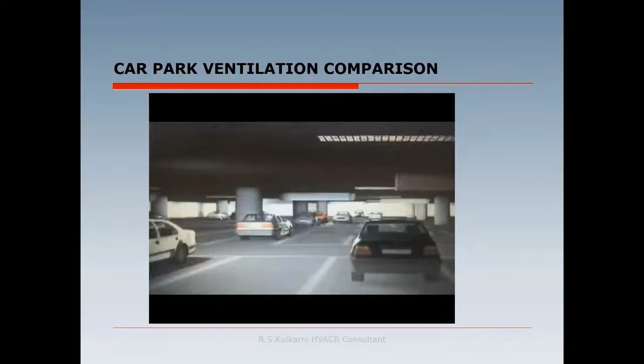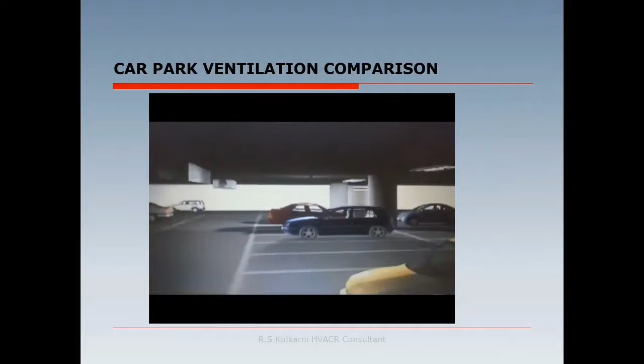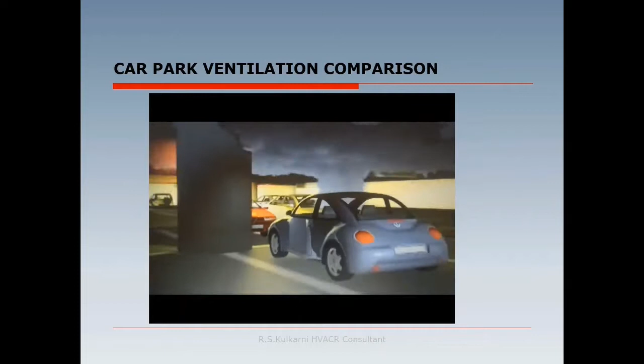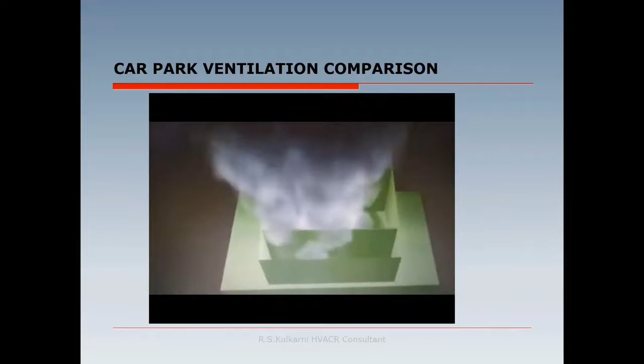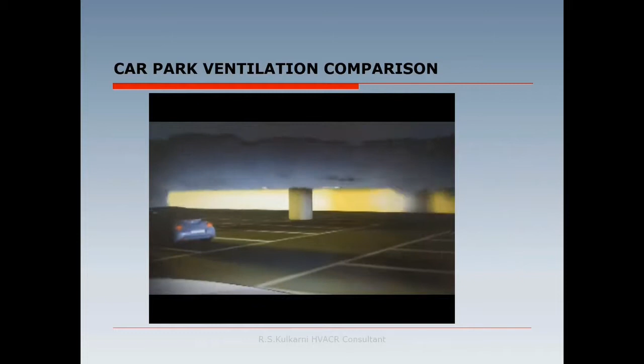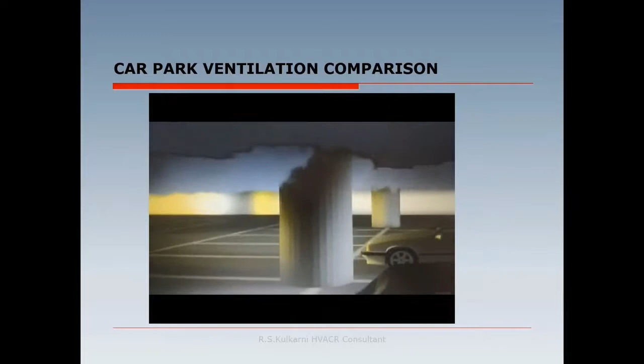Now I have made one slide for this, showing how the ductless ventilation system will behave when we have smoke generated in the parking. Now see, the fire is propagated at one point and starts generating smoke. This is the principle of the jet fan. They are just throwing the air along the air path. You see how the smoke levels are properly maintained in this. We have good visibility.